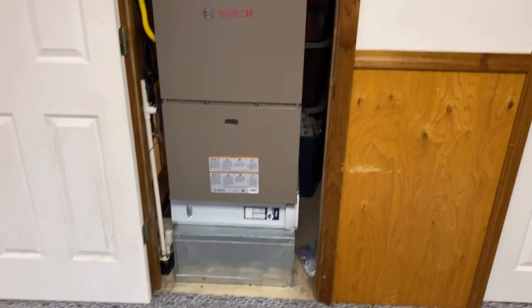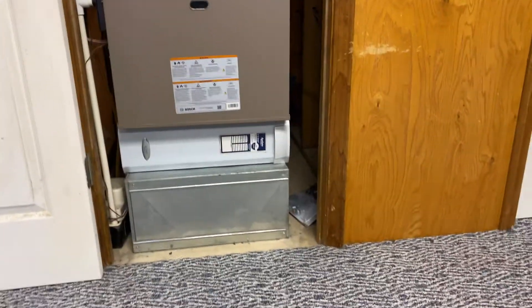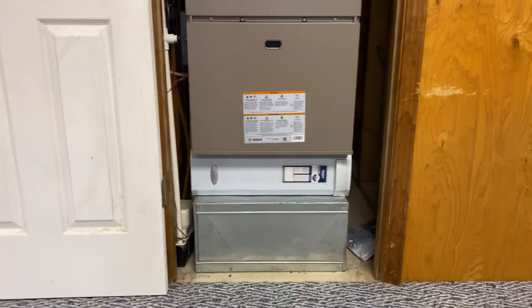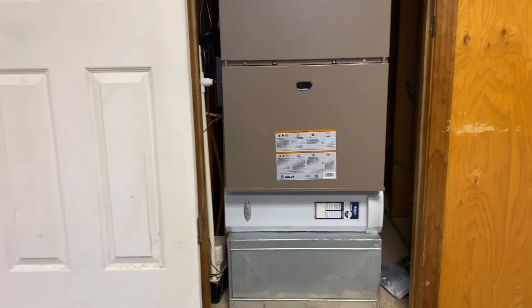We did go with the Aprilaire filter - I love Aprilaire, as you'll come to find in the future. There's an opening on each side, and like I said we had about 0.55 to 0.56 total static pressure, so that wasn't too bad.